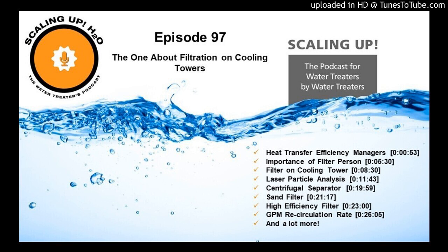So I think the first guy that came up with it was in Western Mass. And what he did is he ran the water crosswise across the filter bed, which brushes the top surface of the filter bed. And instead of storing the particulate that's removed in the bed, which a straight through filter does, the cross flow type filter stores all of the particulate up above the bed. So during filtration, high efficiency filters are not plugging up the bed. They're continually brushing the bed.